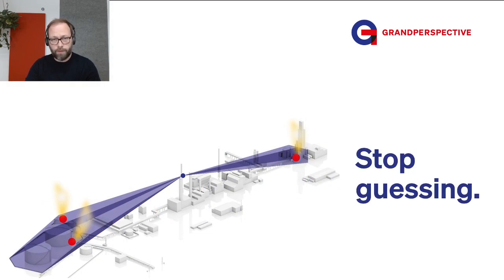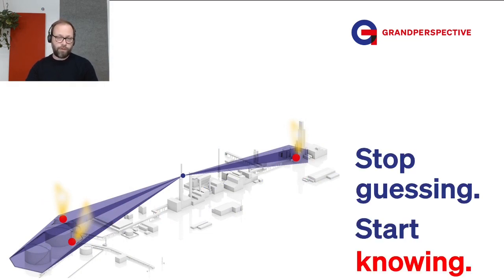So the concept of the Scanfeld early warning solution is to monitor large areas up to entire chemical parks, that is production areas, storage facilities, systems of pipelines, unloading stations, from the distance of roughly up to a kilometer per sensor unit, giving you the opportunity to monitor even large areas with a very small number of those sensor units. And that is done by a technology that is called remote sensing based on FTIR spectroscopy.